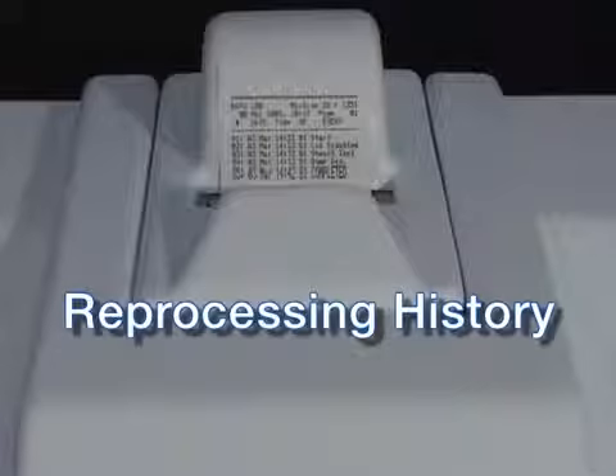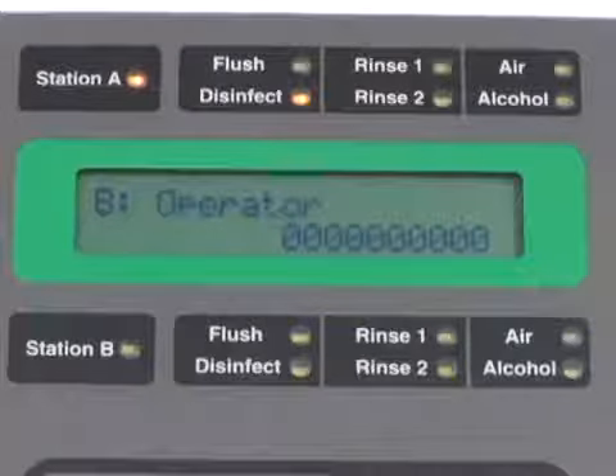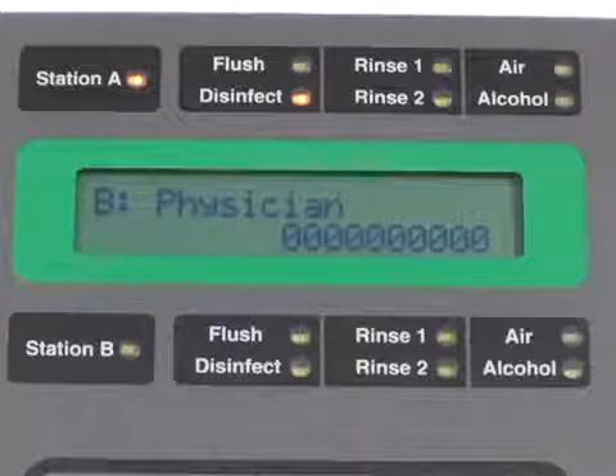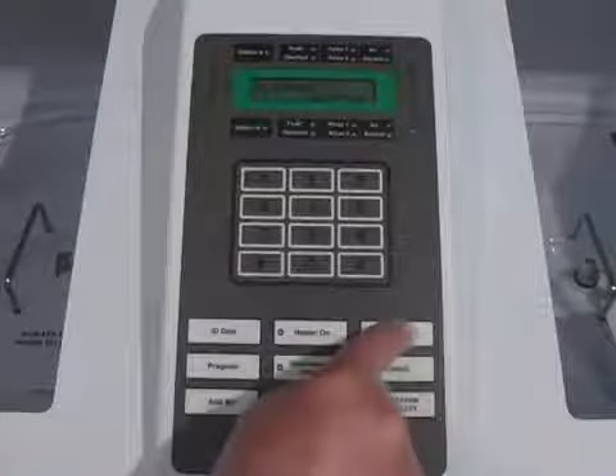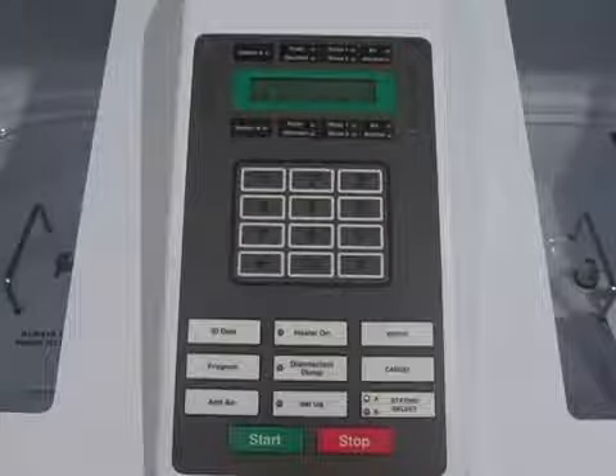Most owners take advantage of the ability of the DSD-201 to provide printed documentation for each reprocessing cycle. The information recorded can be the endoscope serial number, operator ID, patient ID, and physician ID. This feature can be skipped, or some fields can be skipped by pressing Enter to pass unused fields. If using DSD data management, the same data must be entered as for the printer. Use the numeric keypad to enter the appropriate ID data. Press the Start key.